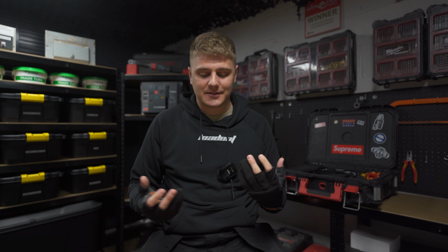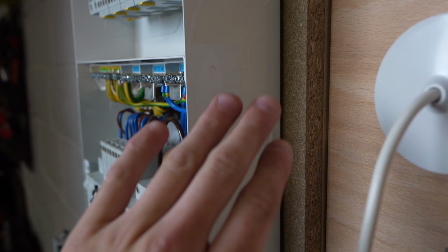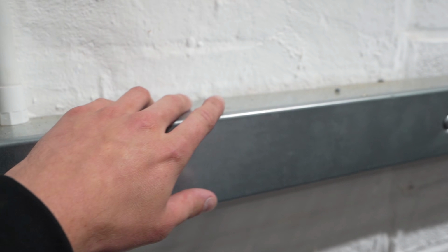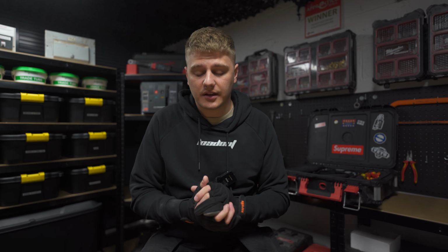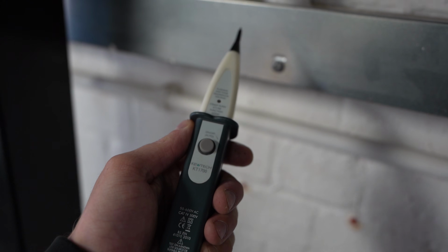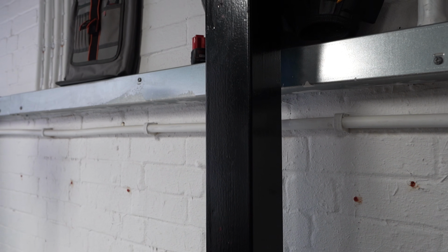The idea is you have an electrical installation with obviously loads of exposed conductive parts, whether that's metal consumer units, trunking, whatever. And under fault conditions, an earth fault particularly, those parts of the installation could rise in voltage. Now you may have a water or gas main that's coming into the building, and this is going to be sat at 0 volts. This potential is actually being introduced from outside of the installation because the gas or water main is running through the ground, which is basically its own earth electrode.